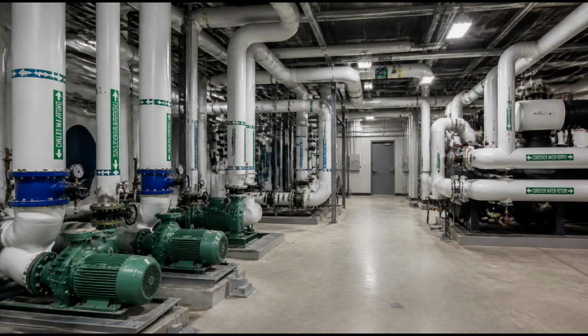A VAV box serving an unoccupied office may reduce its airflow to a minimum set point, enough to prevent stagnation, but far less than what would be needed during business hours. Across a building with many zones, this dynamic adjustment is happening constantly. Some zones are opening up as people arrive for the day. Others are modulating as conditions shift. Still others are quietly idling, maintaining minimal airflow in spaces that will not be occupied again until tomorrow.